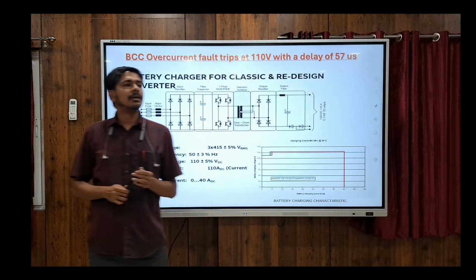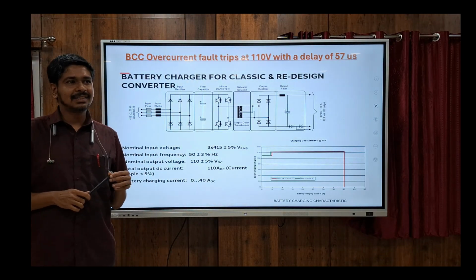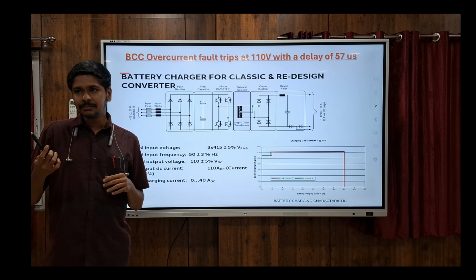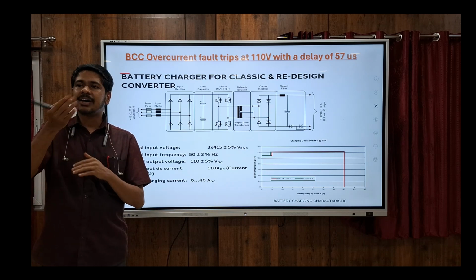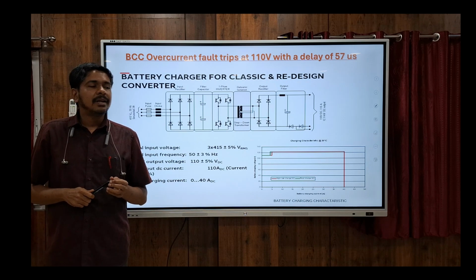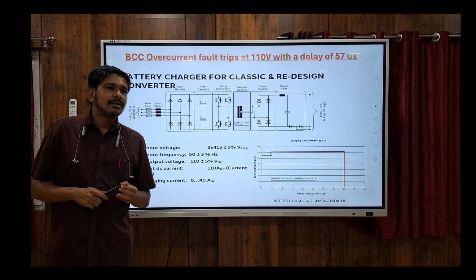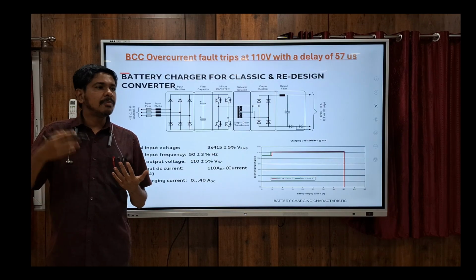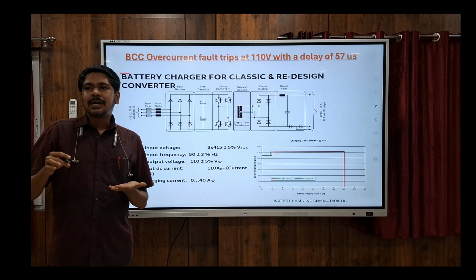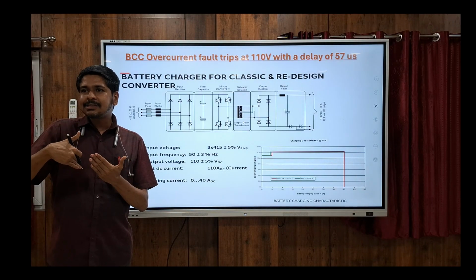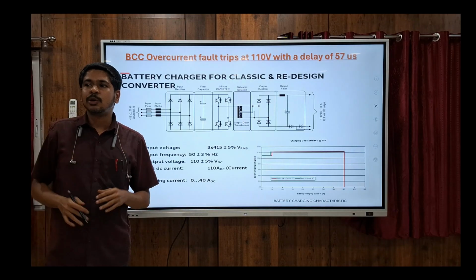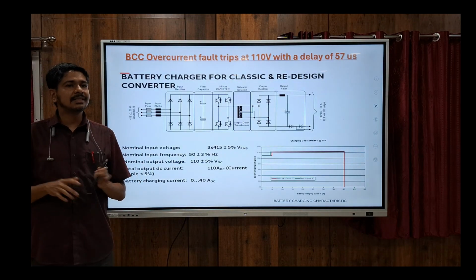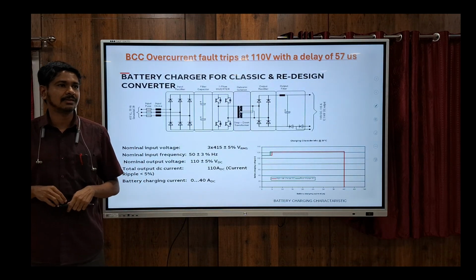Then DC link over voltage, in ABB, is given as 730 volts protection. If that limit is reached, the battery charger will trip. Then voltage values: initially I told you a warning will be given at 92 volts and 86, then at 82 it will shut down. Actually, at 86 itself we are getting shutdown cases.